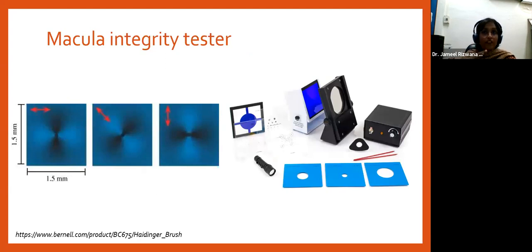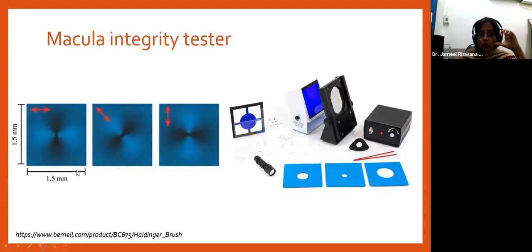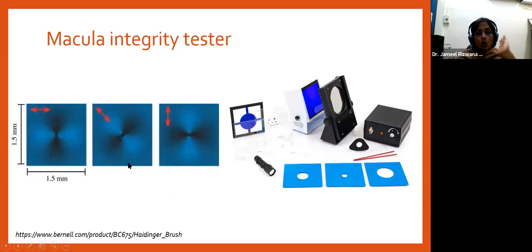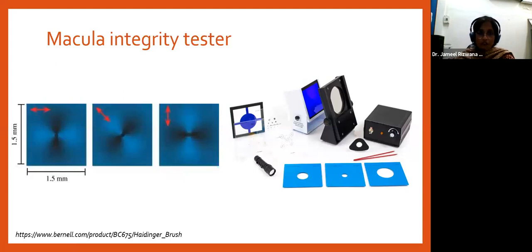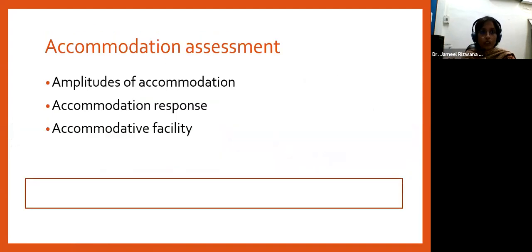The Macular Integrity Tester (MIT) is a modification of the conventional Haidinger's brushes — an entoptic phenomenon-based test. When looking through blue filters, the patient sees a propeller shape. The propeller center corresponds to the fovea, and its position relative to the fixation point indicates eccentric fixation. We use this not just for estimation of eccentric fixation but also in treatment — to break anomalous correspondence and eccentric fixation patterns.